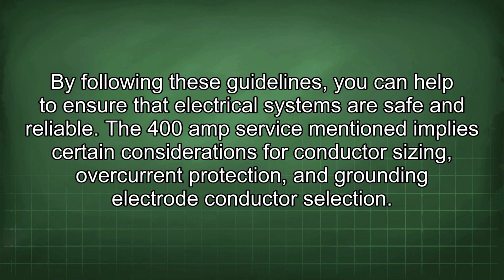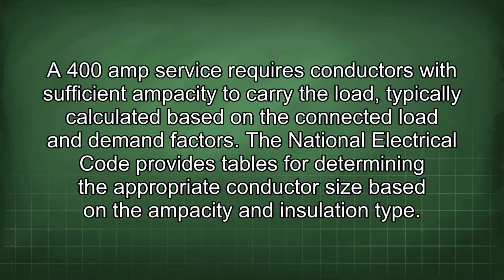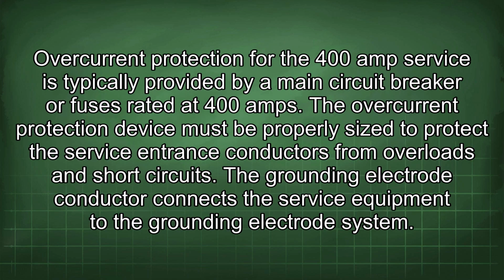The 400 amp service mentioned implies certain considerations for conductor sizing, overcurrent protection, and grounding electrode conductor selection. A 400 amp service requires conductors with sufficient ampacity to carry the load, typically calculated based on the connected load and demand factors. The National Electrical Code provides tables for determining the appropriate conductor size based on the ampacity and insulation type. Overcurrent protection for the 400 amp service is typically provided by a main circuit breaker or fuses rated at 400 amps.